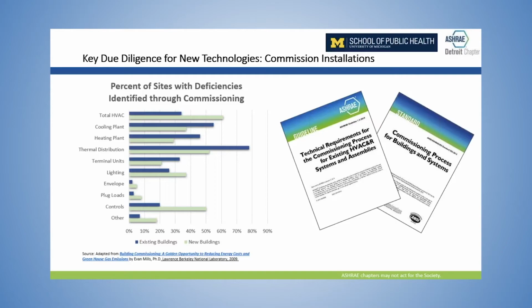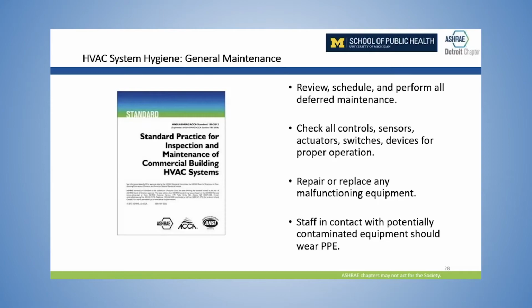So one of the things that Regina and Stuart both mentioned was that often one of the big problems in schools is deferred maintenance, right? Which is really a nice way of saying that broken things remain broken. But we know that the sole purpose of the HVAC equipment is to provide a good indoor environment that supports student learning. Right, so this HVAC equipment can only do its job if all of its parts work. The most common unmaintained components in the HVAC system are the actuators and the sensors, particularly those on economizers that control the amount of outdoor air that's brought into the building, right? And this is one of the key components. Outdoor air is one of the key components of indoor air quality.